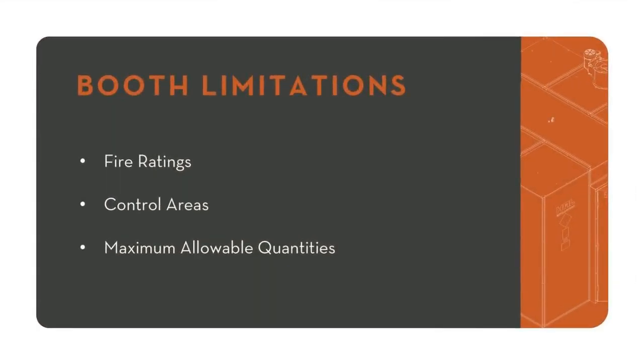So now we'll move into limitations of the booth. These are not definitive limitations, but these are kind of standard limitations that you'd see on a basic extraction booth. So these things, fire ratings, control areas, and MAQs, all go hand in hand. Our booths at least don't have a standard 1 hour fire rating. But when you have a 1 hour fire rating on your 1-hour enclosure, that creates its own control area. So as far as a control area goes, each given control area is allowed to have 150 pounds of class 1A flammable solvent. So something like butane, you could have 150 pounds. By placing it into that control area, or by placing it into that ventilated space, you then can double it. By placing fire suppression on that system, then you can double it again, right? So now you have an allotted 600 pounds of butane.